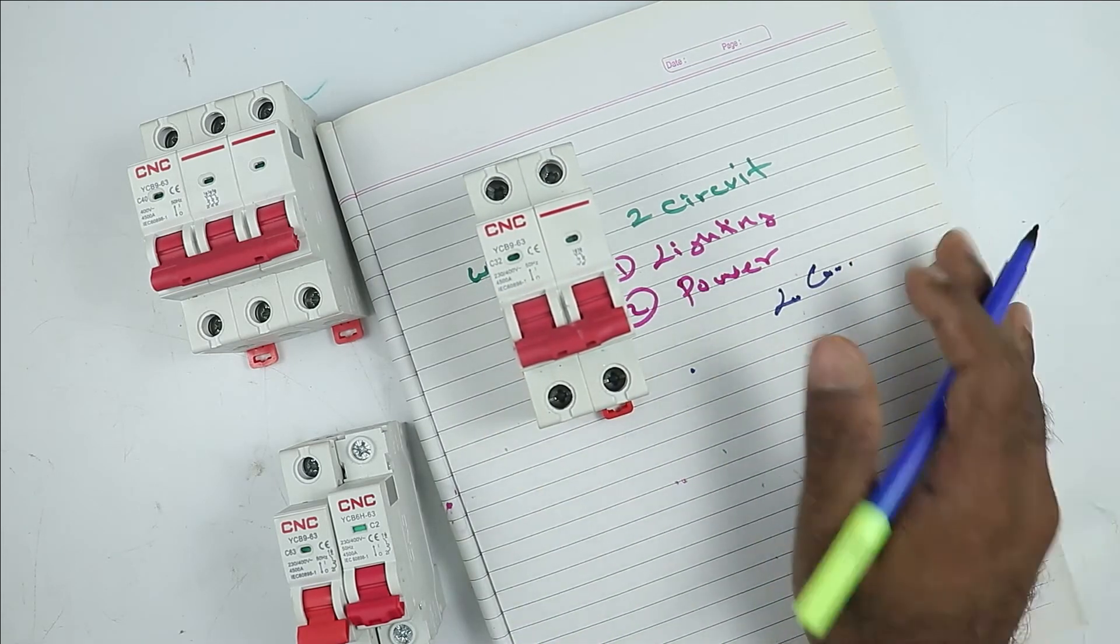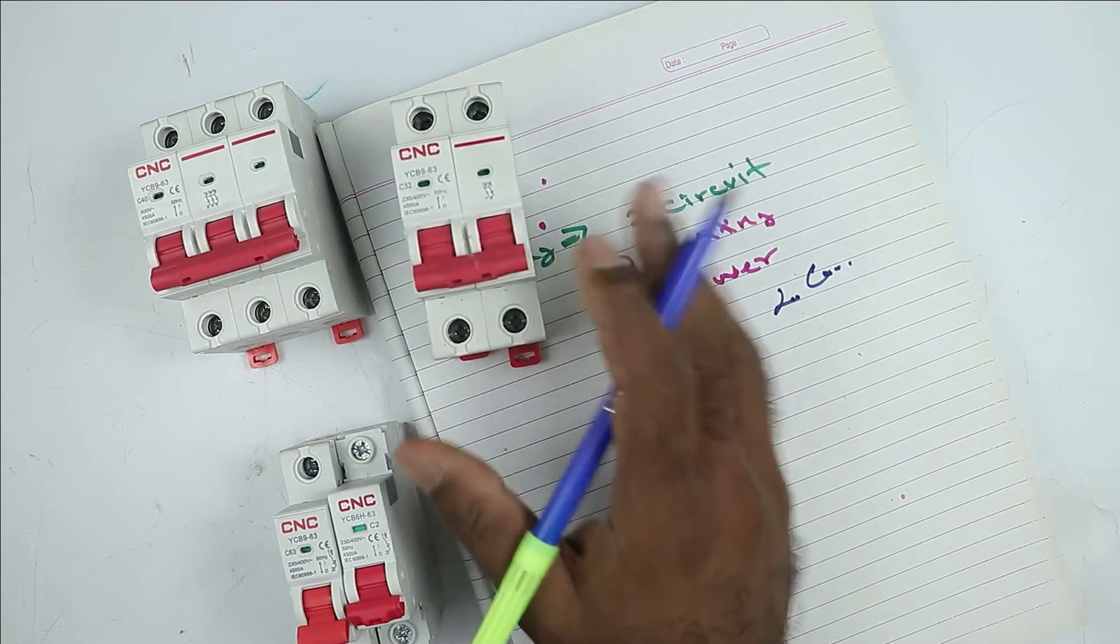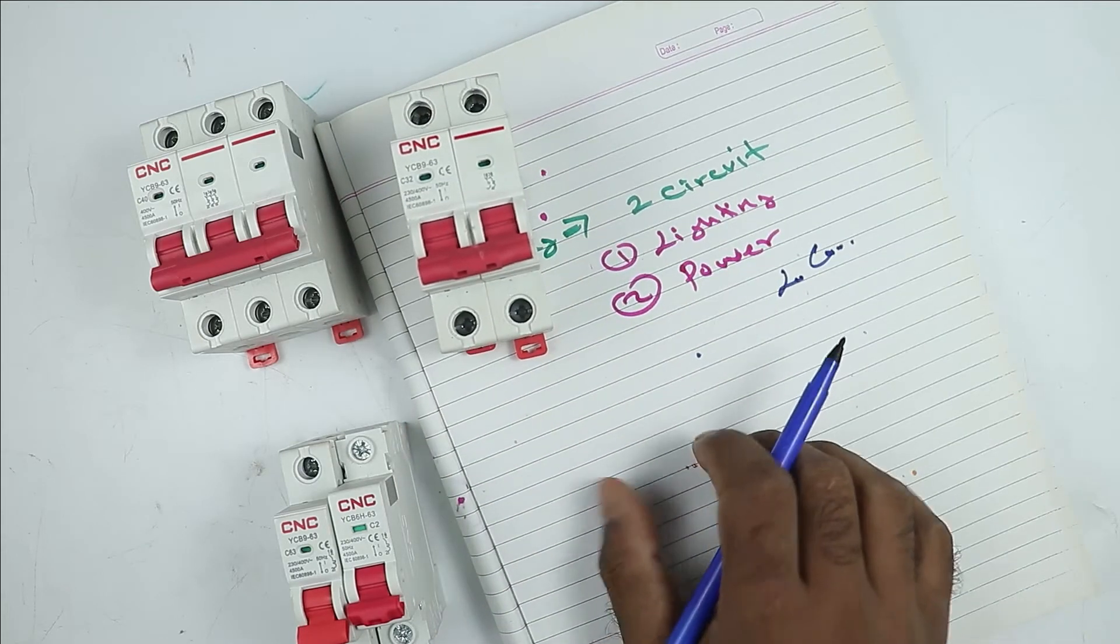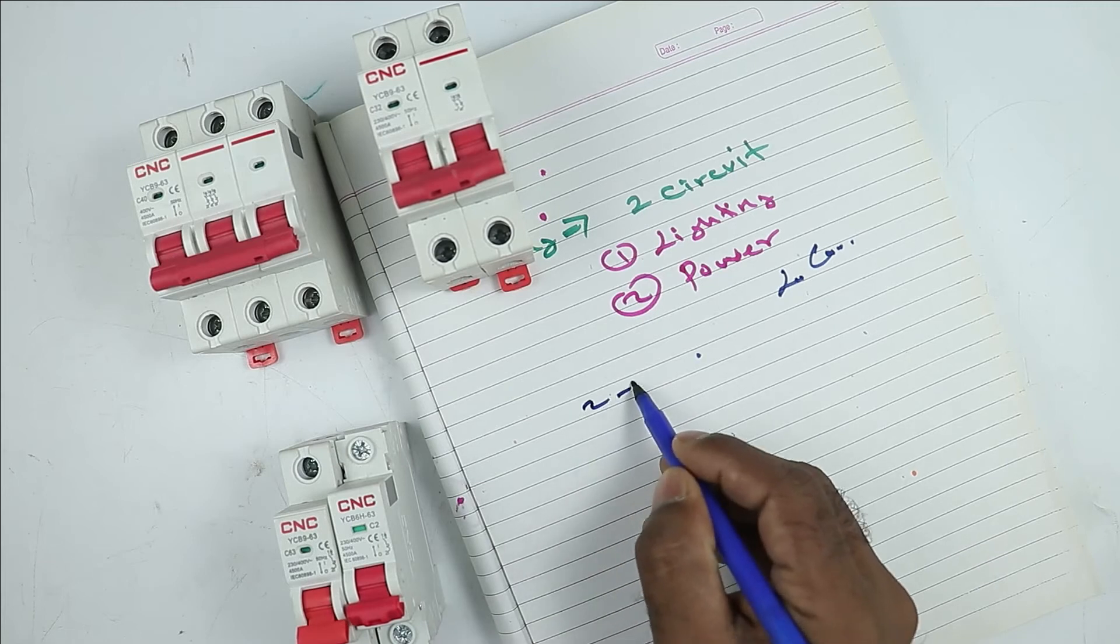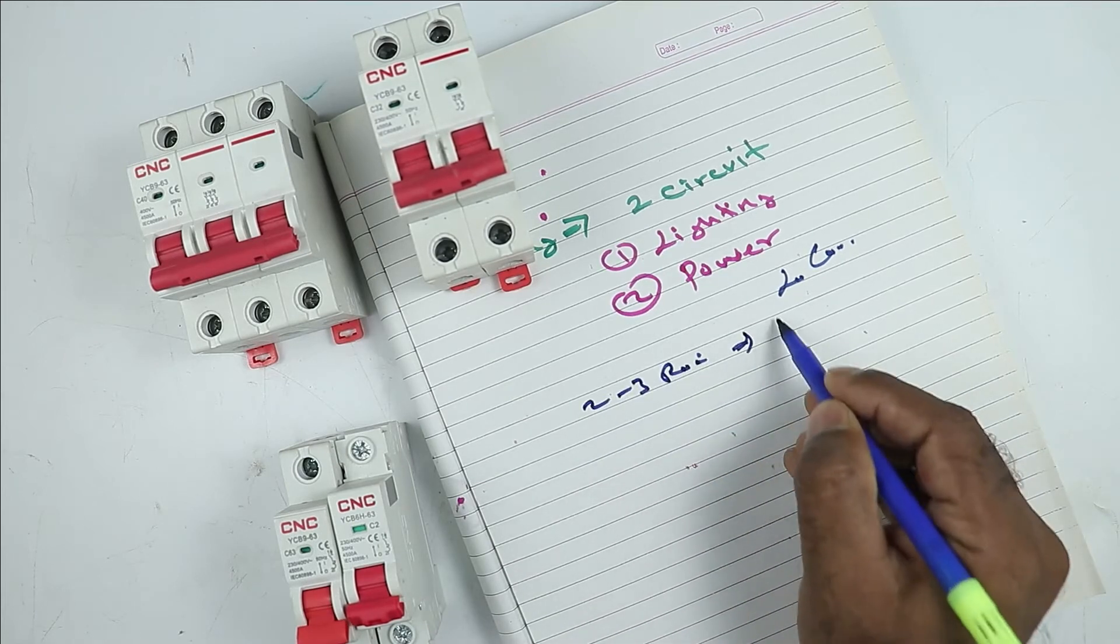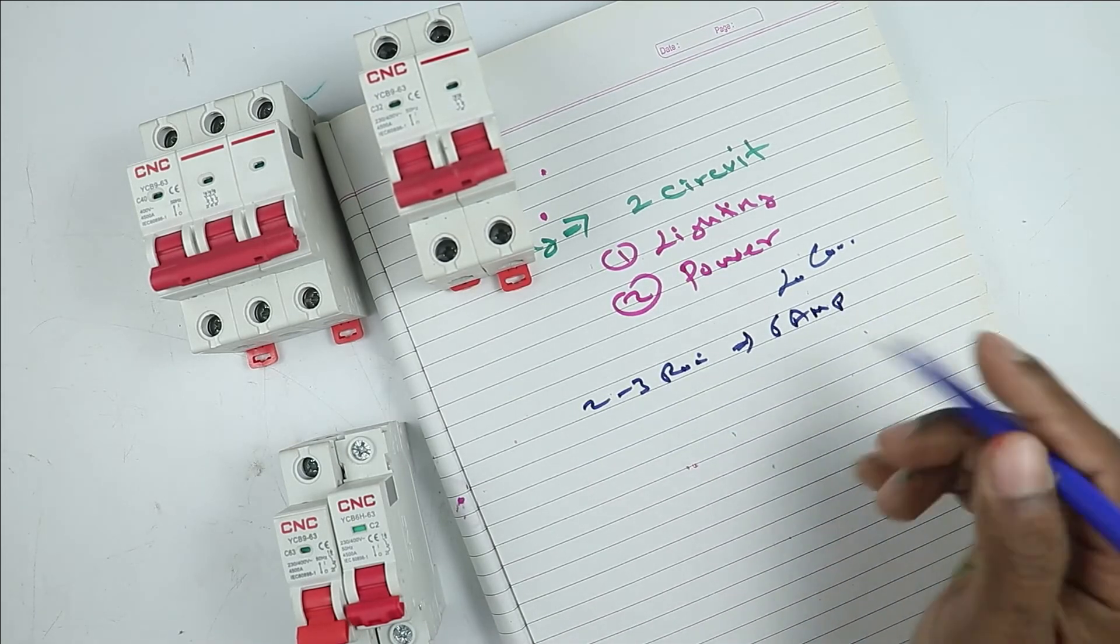To find out the required rating of MCB, a calculation is needed. If you don't want to go for calculation, there is also a simpler way. If only 2 to 3 rooms are there in your home, then you can use 6 ampere MCB for lighting circuit.